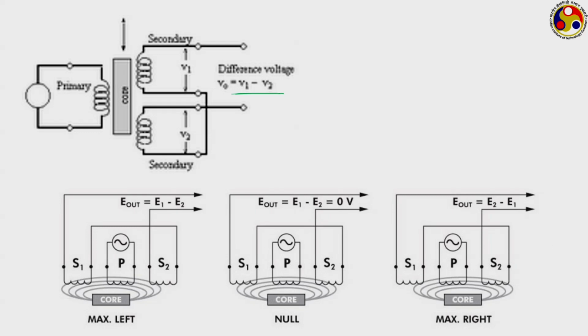This is how they operate. When the core is at the null position, both coils have the same voltage induced, so E out equals 0. When the core moves towards the left, the mutual inductance in S1 becomes larger than that induced in S2, so E1 is higher than E2, giving a net value of E1 minus E2.